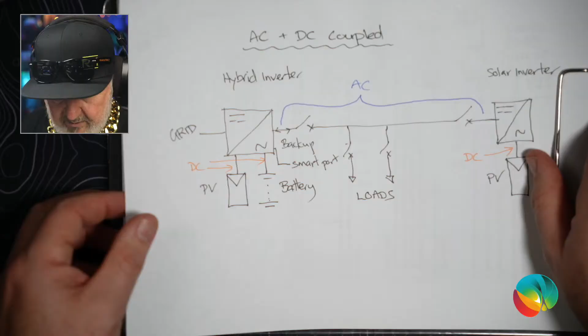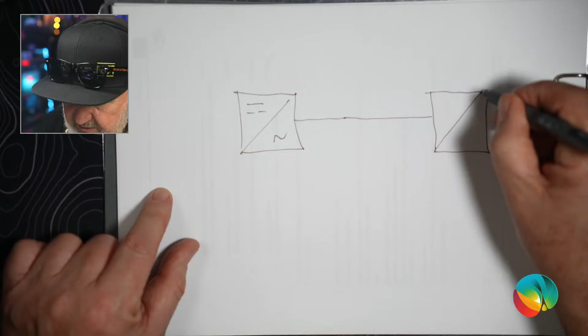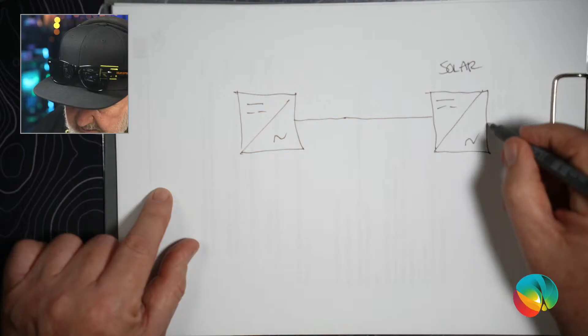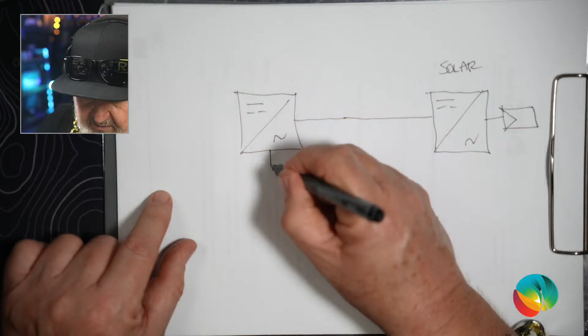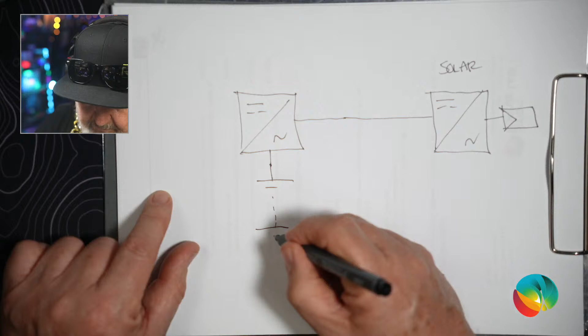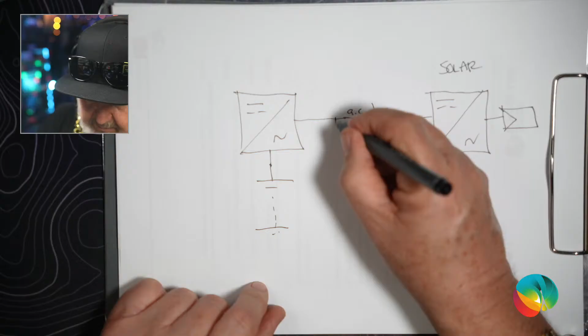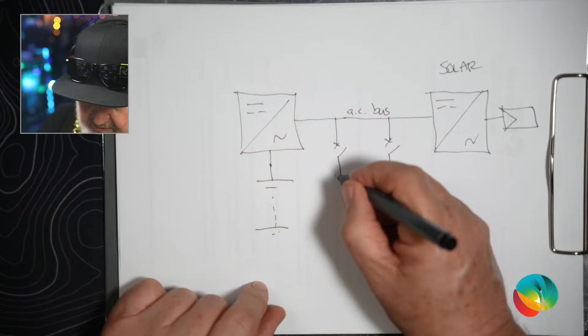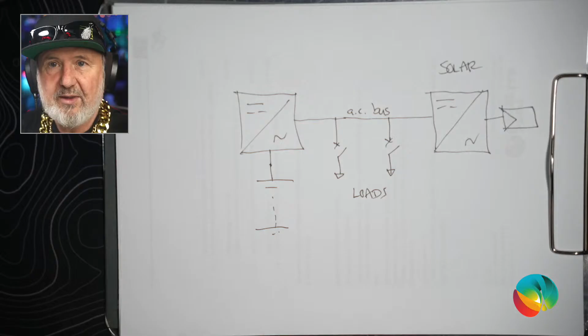Okay, here we go, this is what I call a black start protection system. This really applies to off-grid. If you've got an AC coupled system, here's our grid forming inverter, and we're connecting it to a solar inverter. That's solar, with some solar panels connected to it. The grid forming inverter has a big battery system. And this is our AC bus here, with our loads coming off it. So that's basically an AC coupled system, what you're looking at there.